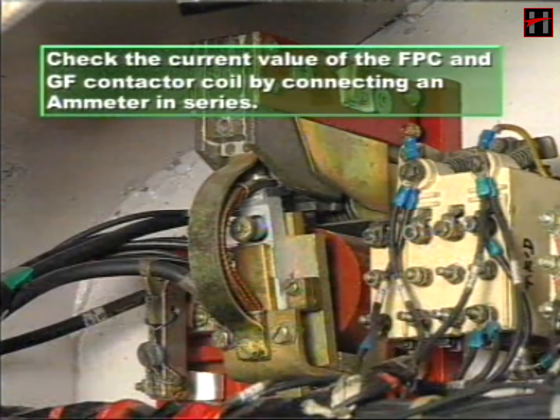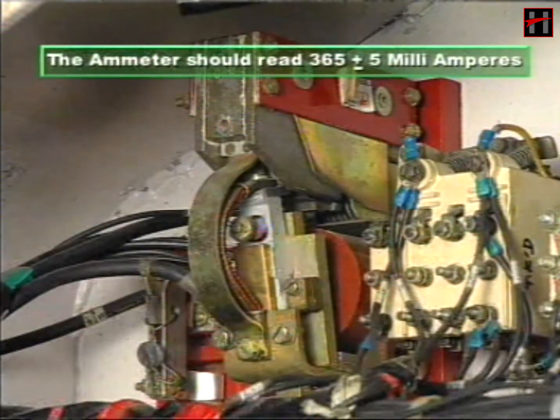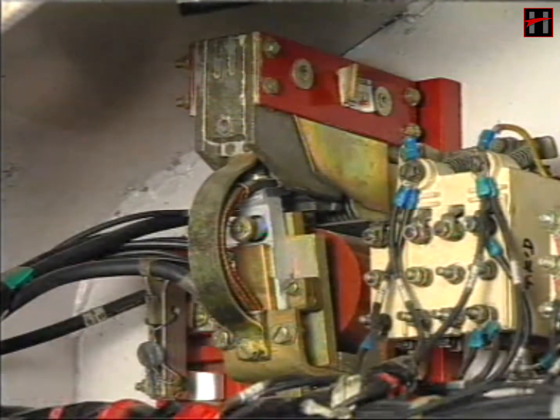Check the current drawing of the fuel pump contactor coil and the GF coil by connecting an ammeter in series. The ammeter should read 365 plus or minus 5 milliamperes.